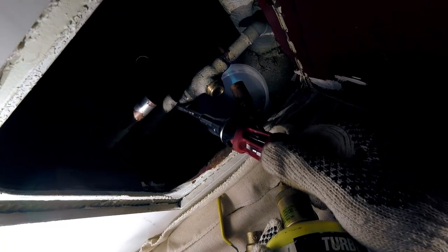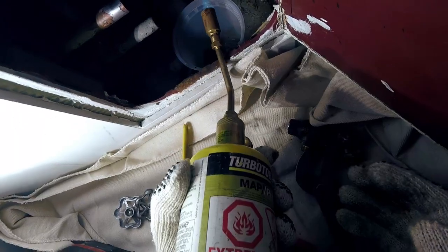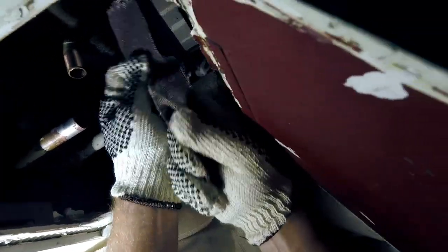So pay extra attention to those areas with your grit cloth, and if you have to, get a small mirror, verify that the pipe is clean if you're not sure. And if you ever see your solder ball up and drip without going into the fitting while you're soldering, most likely you have an area that is not clean, not pasted, or worse, both. Do yourself a favor, take the fitting out right away and start again by cleaning everything thoroughly.